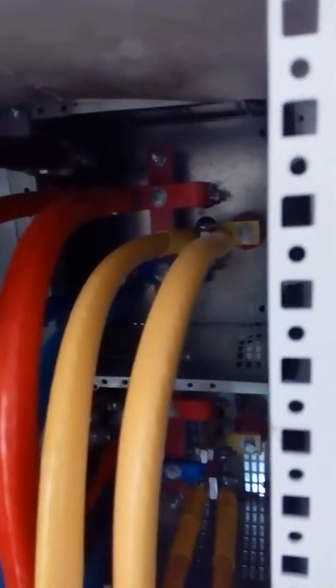This is the back side of our MDB — this is the Main Distribution Board. This is the same finished product — after they finish this one, see. This one not yet finish, still space — see my hand there. But later on it will become same like this one. Already finish — you cannot put your finger from here. So it means this is already the finished work for making the gland termination, putting the lugs, everything.